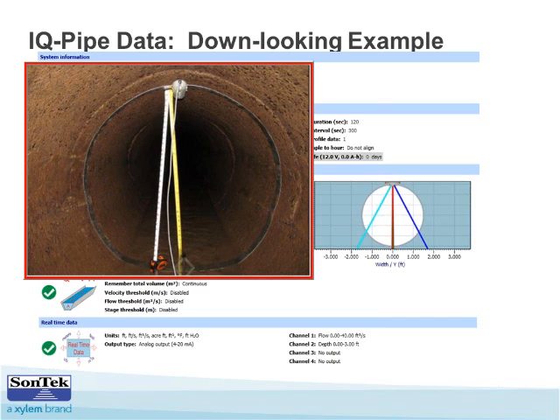But it's always best, since this isn't always the case, to take a measurement in the vertical and the horizontal, and sometimes even at 45 degrees, then average them, because most of them are not true. There are differences in the diameters, most likely due to how the pipe was installed many, many years ago.